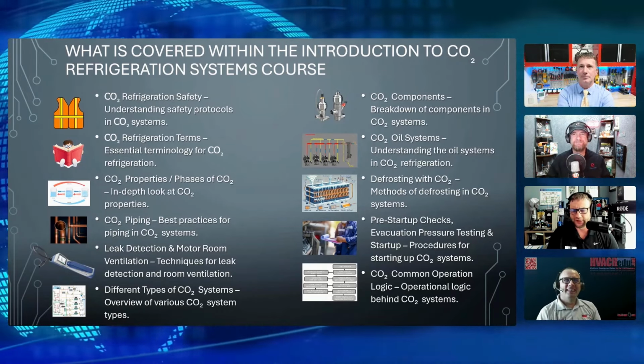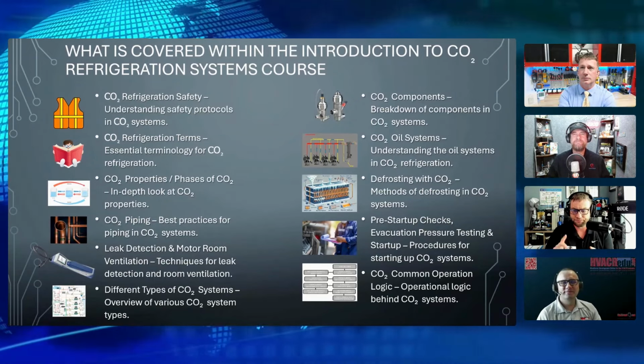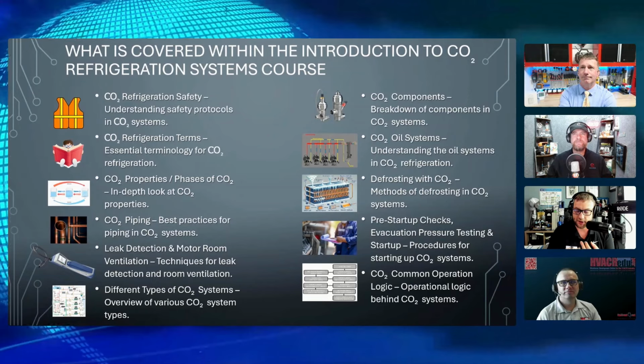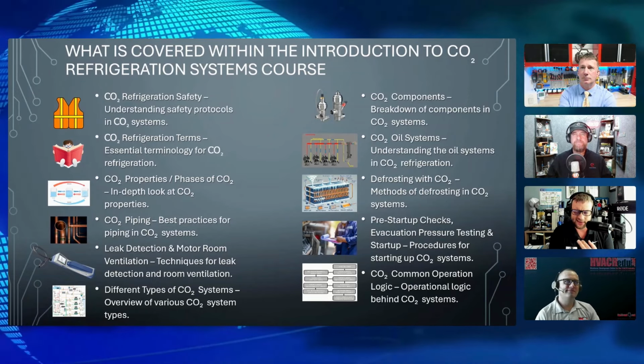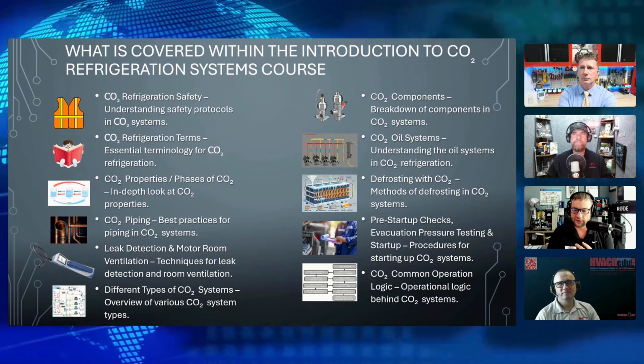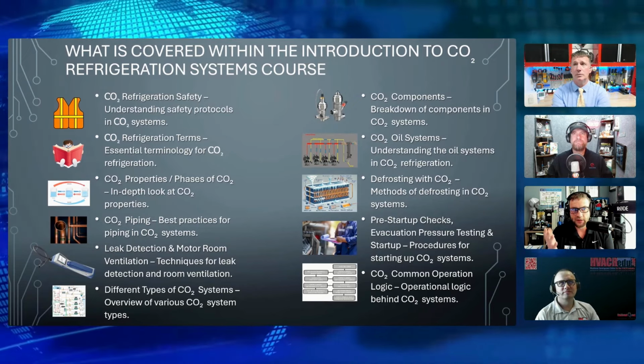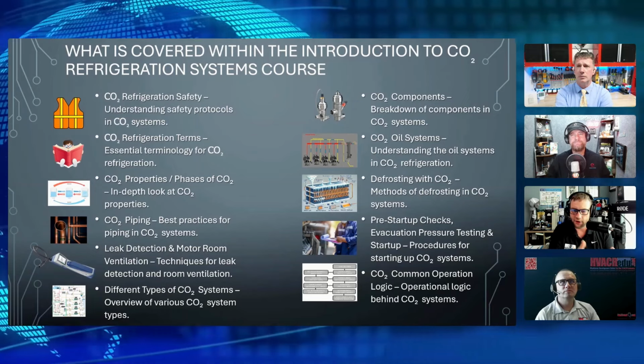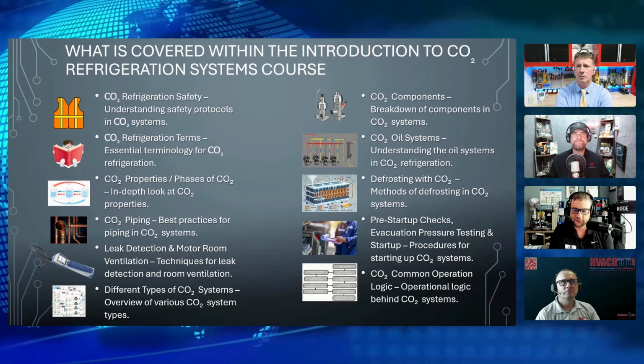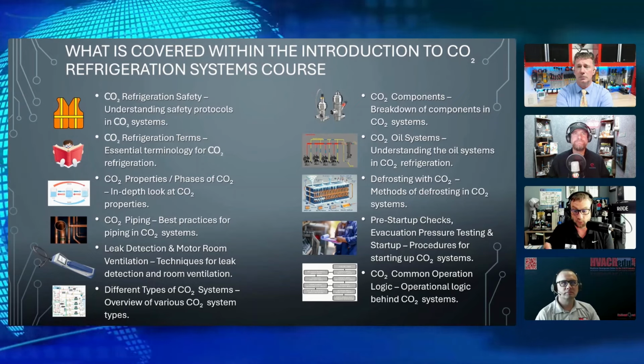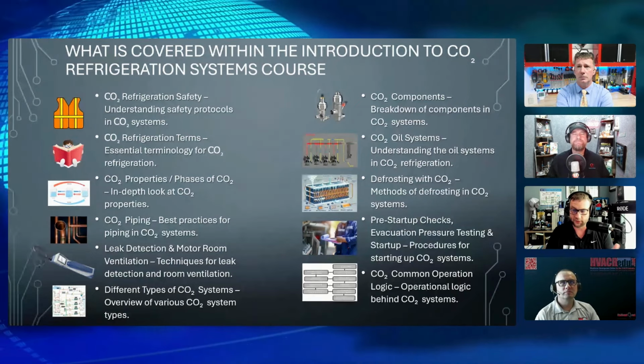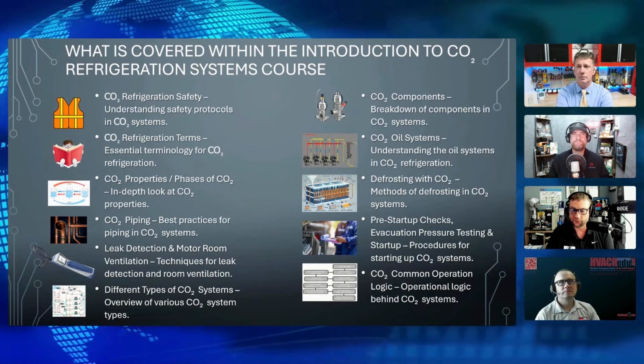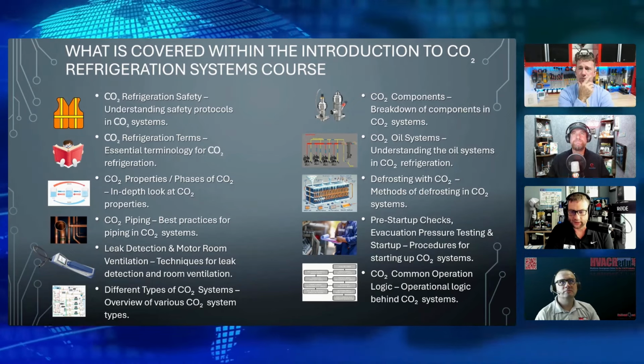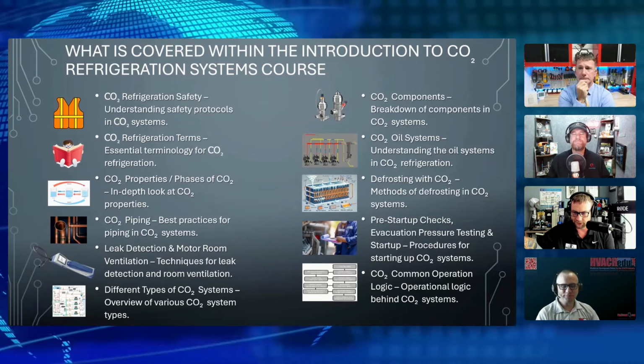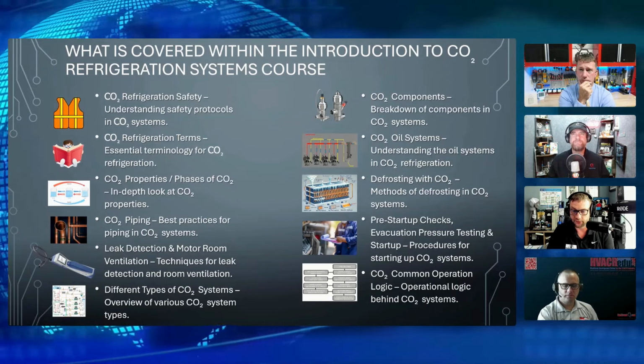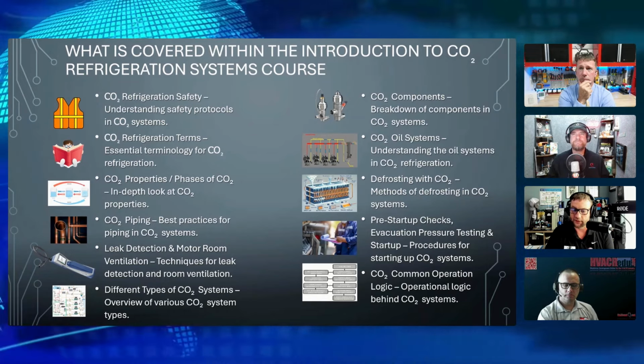Defrosting with CO2. Really not any different, right? Usually off time, electric, and hot gas. Hot gas, because of the cost factor, is used frequently, but not nearly as frequently as electric right now. The manufacturers are still trying to figure out where their guidelines are. So right now they're making their cases for X PSI, right? When they finally get certified, whether it be 90 bar or 120 bar, whatever they actually decide on, at that point I think hot gas will be more prevalent and come back into consideration. Exactly. It's still being used in the very big commercial systems and some bigger supermarkets as well, but not as frequently as electric defrost, right?